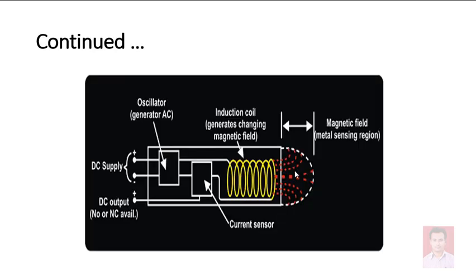Looking at the construction: the metallic tube has an oscillator that generates an AC signal, a current sensor that senses the change in current, and a DC supply. The output is connected to a relay — normally open or normally closed depending on the requirement. There is a coil that generates a changing magnetic field, and within the active surface range, that magnetic field is generated to sense the metal object.